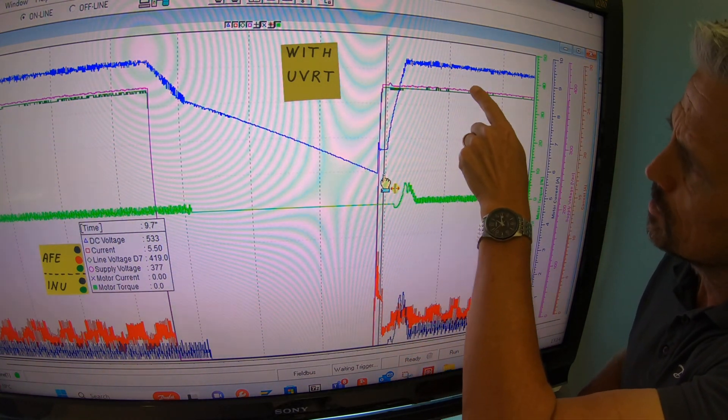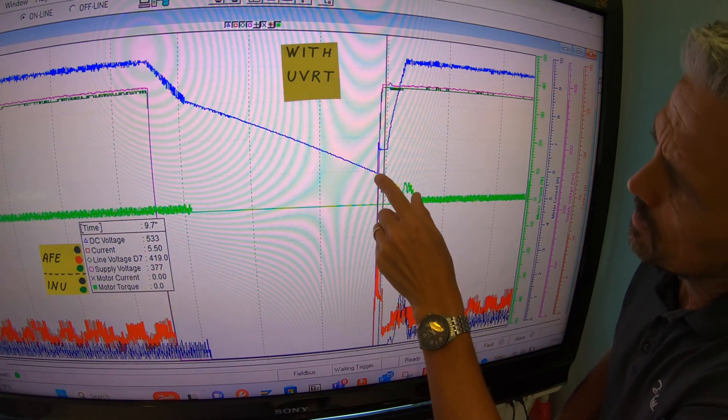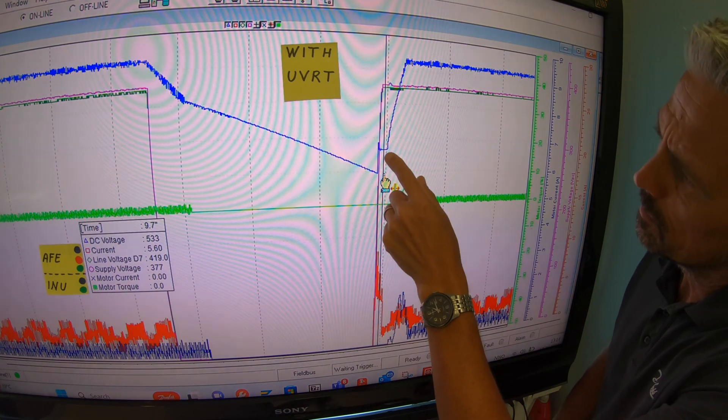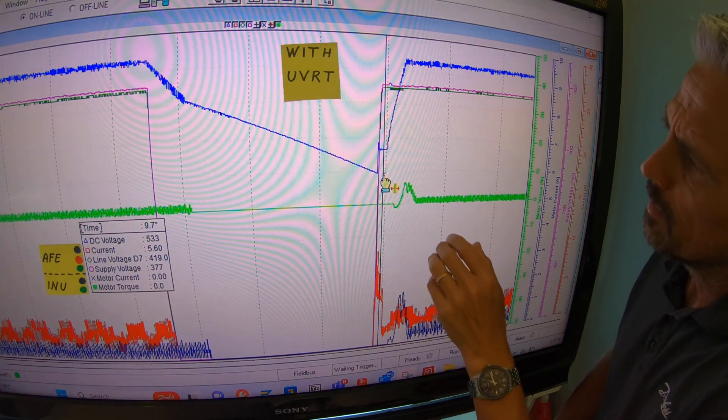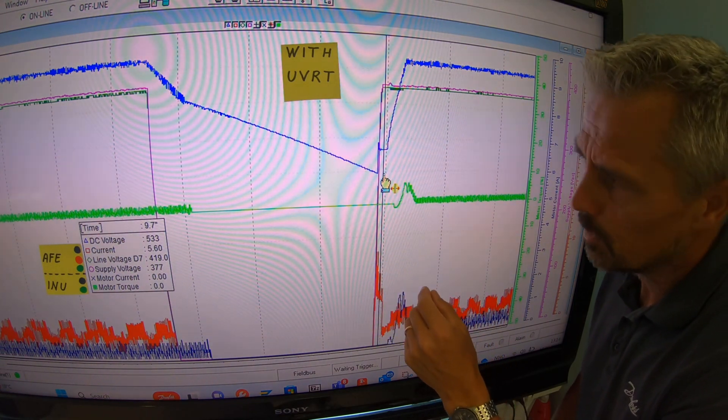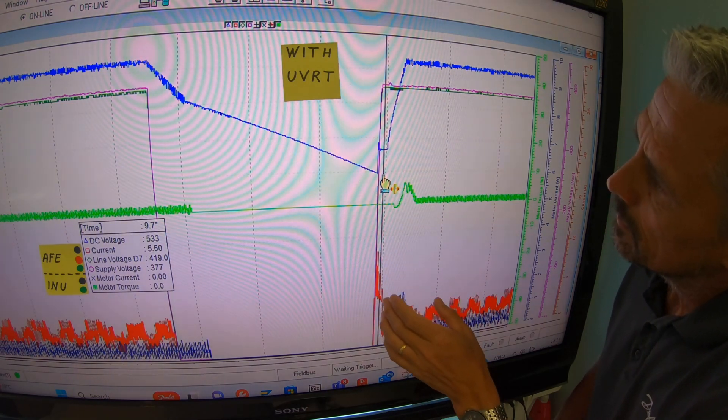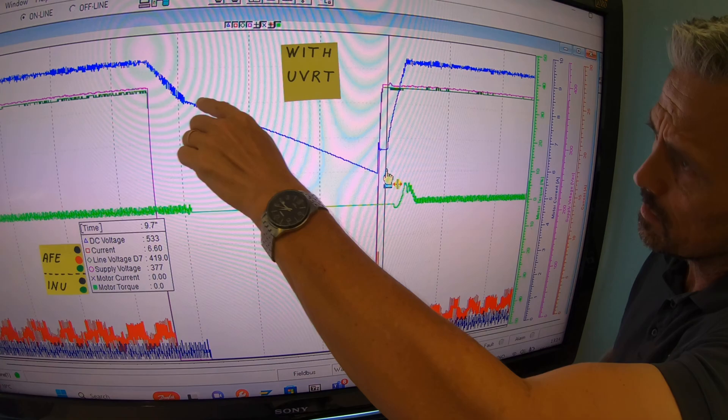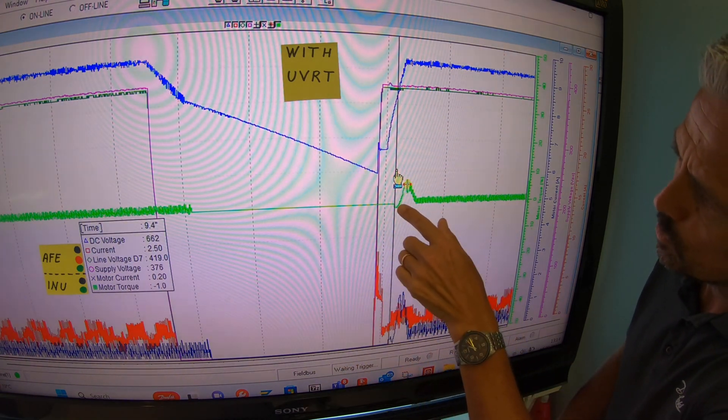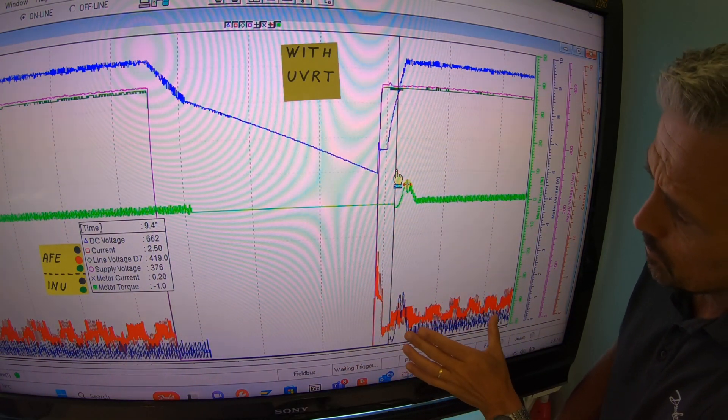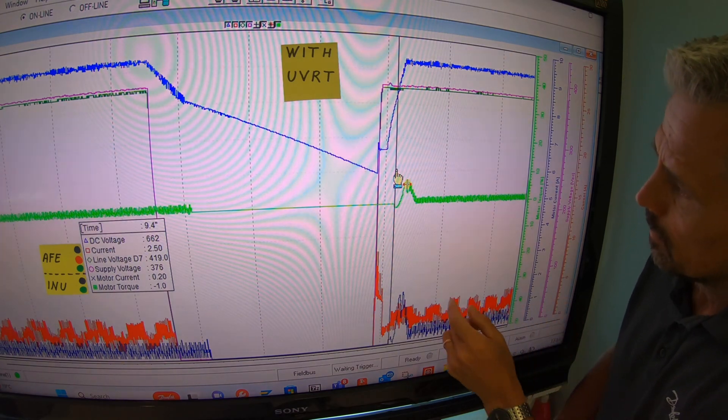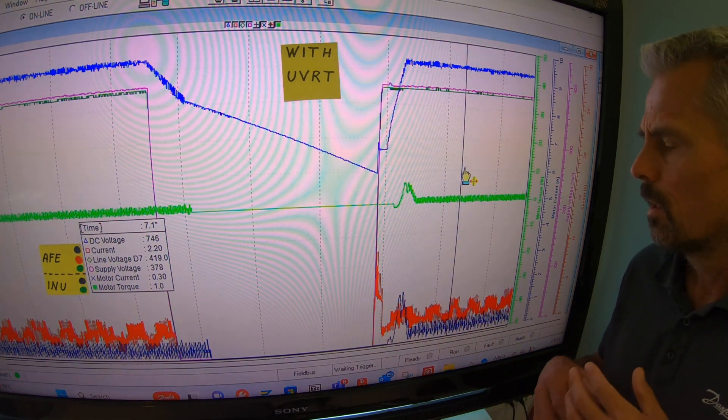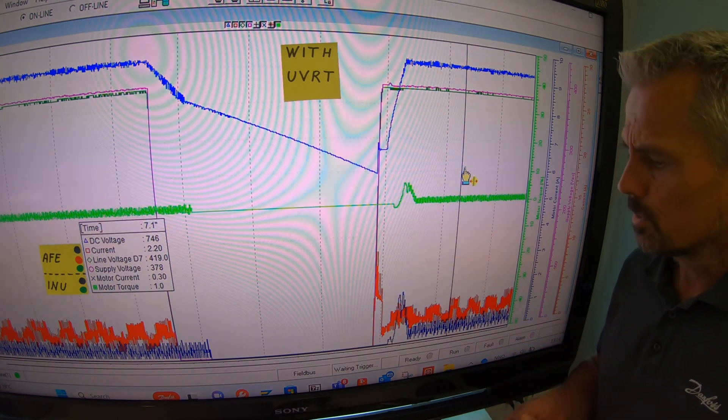Here the AC ship grid is restored. First thing happening is the pre-charge and the freewheeling diodes. They take the voltage up to this level. Then after a pre-defined front parameter time delay, then the active frontend starts producing the DC link. At 650 volt, consumer kicks in back. Now the ship propeller is pulling a current, a torque, and the ship is back into full operation of critical function.